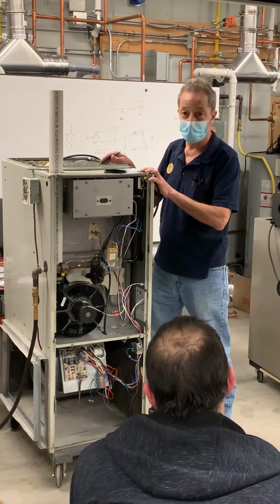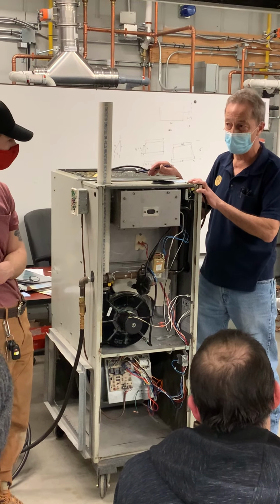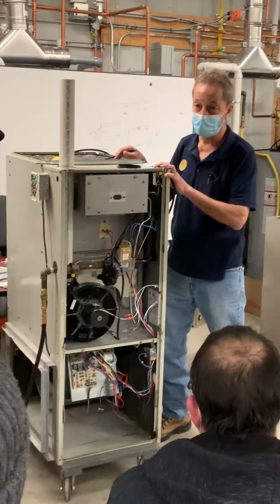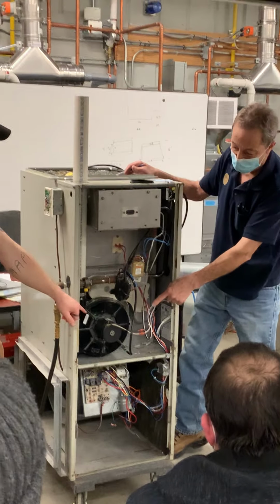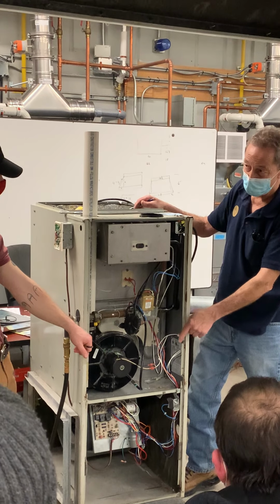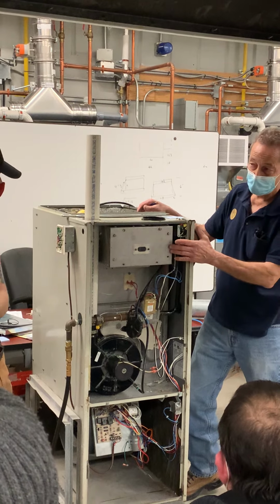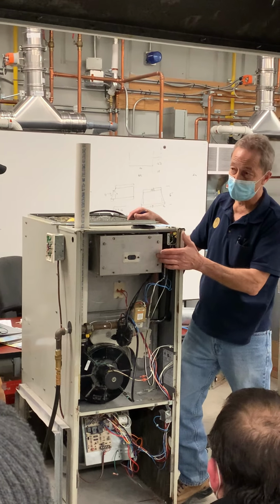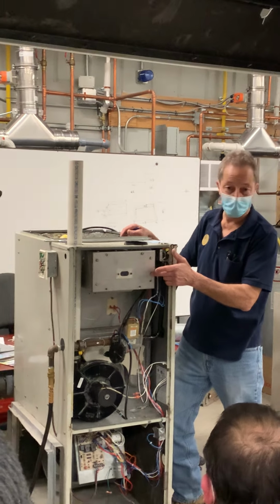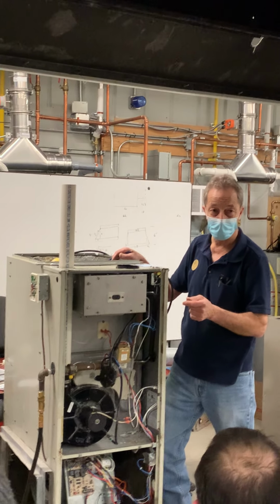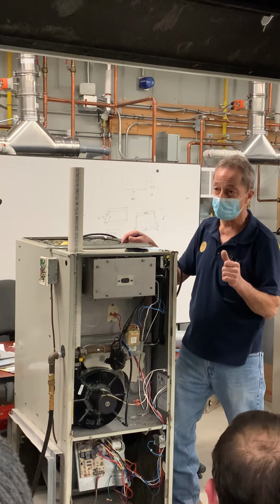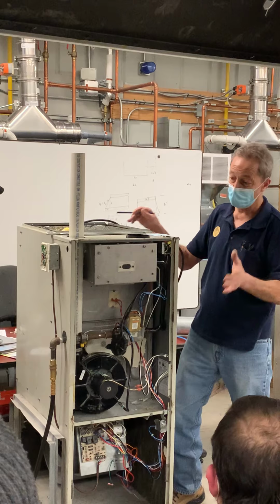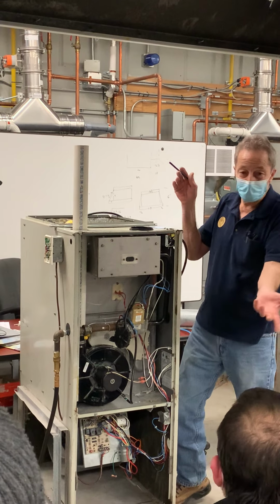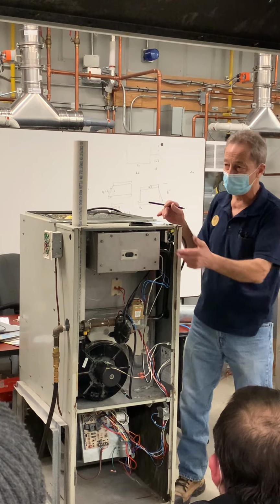If I have a blocked secondary heat exchanger, what happens to the pressure? More negative. This would get more negative, correct. And then I guess nothing really would be happening up here. Well, this won't get as negative as it was before. They're not sucking enough through. Flame rollout? Yeah, and you'll get the flame rollout. But this one closed, if that was happening, it's still going to close. So do I have a flame rollout on this one?